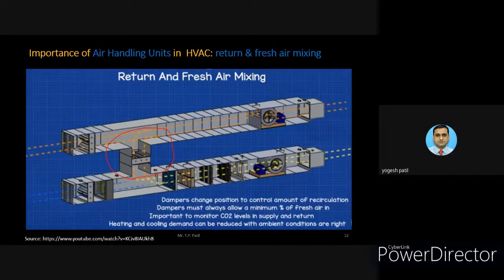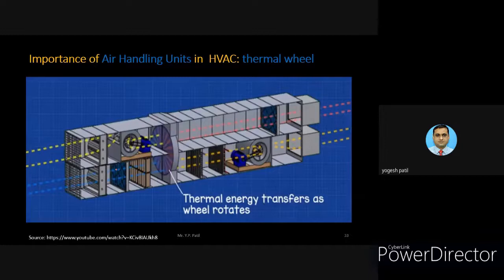If more warmness is required in the rooms, the return air can be used with the help of the damper. This is the damper. The damper can be opened to some amount, so that the air can be mixed with the inlet air. This is the inlet air. It gets mixed with this, and this is the exhaust side, and the remaining will be exhausted out. All these different types of AHUs are available in the market.